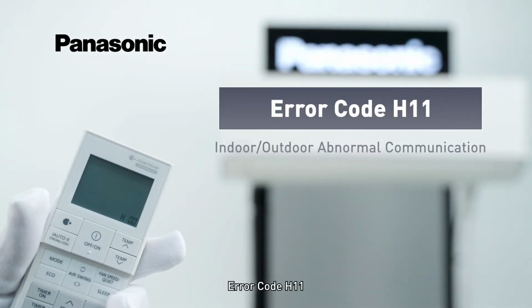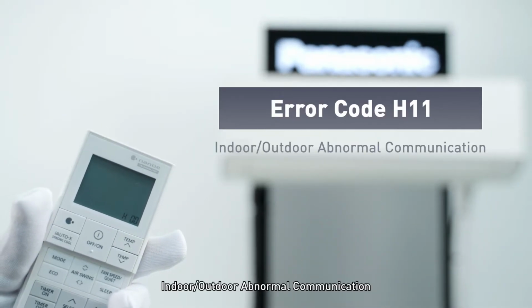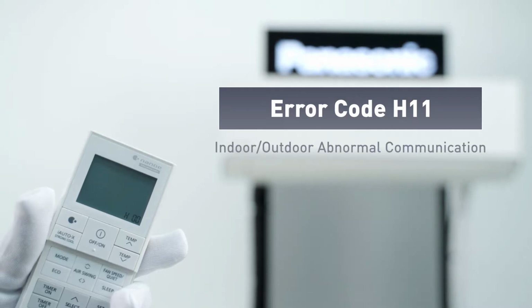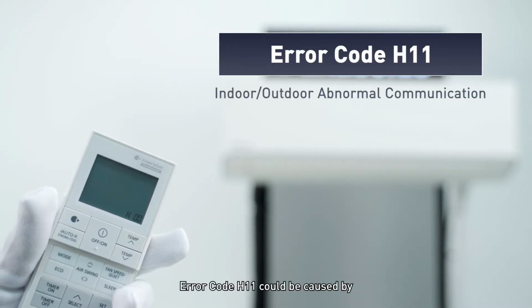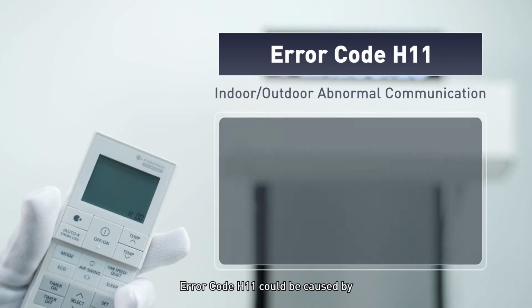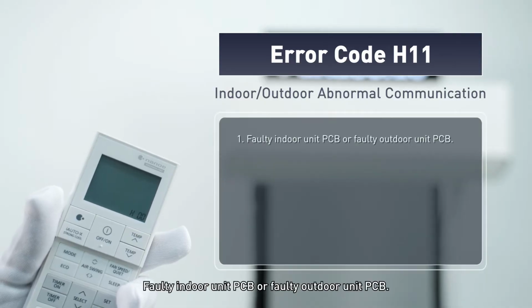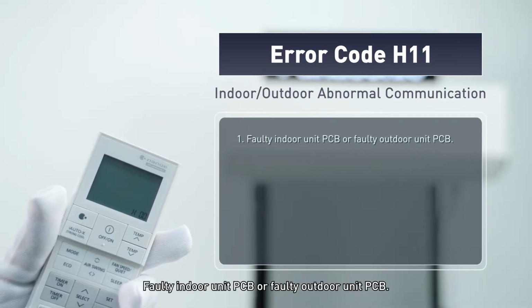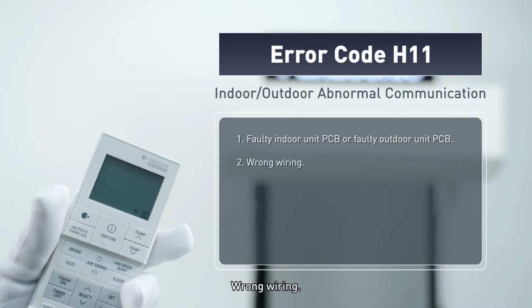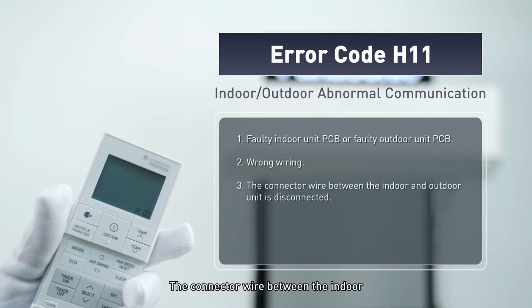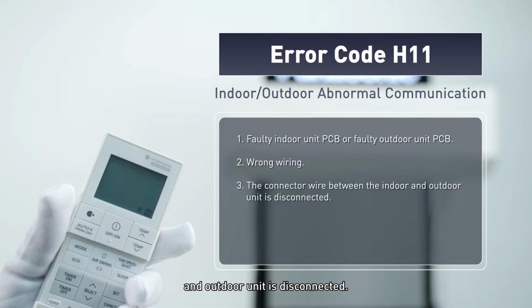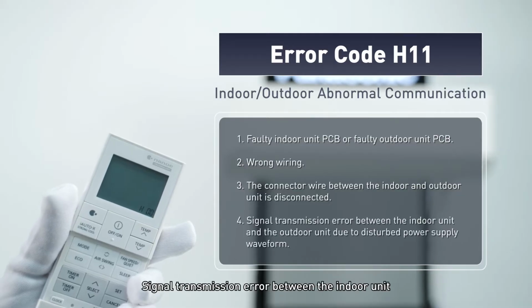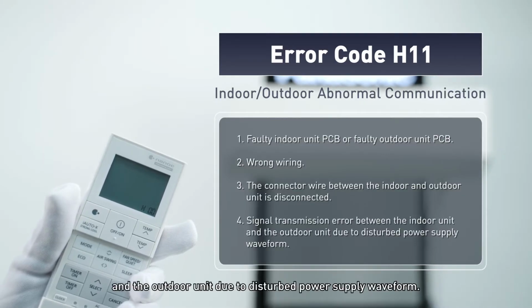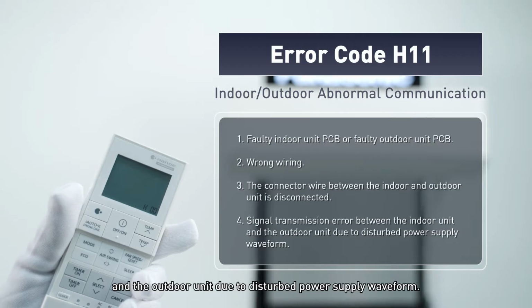Error code H11. Indoor, outdoor abnormal communication. Error code H11 could be caused by faulty indoor unit PCB or faulty outdoor unit PCB. Wrong wiring. The connector wire between the indoor and outdoor unit is disconnected. Signal transmission error between the indoor unit and the outdoor unit due to disturbed power supply waveform.